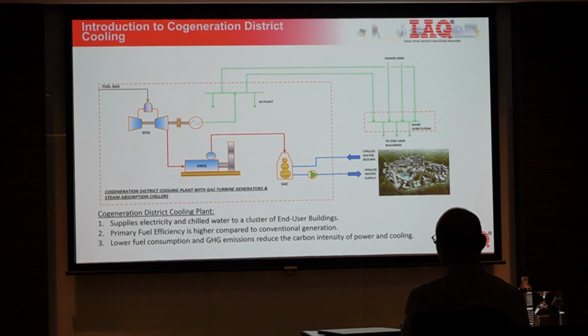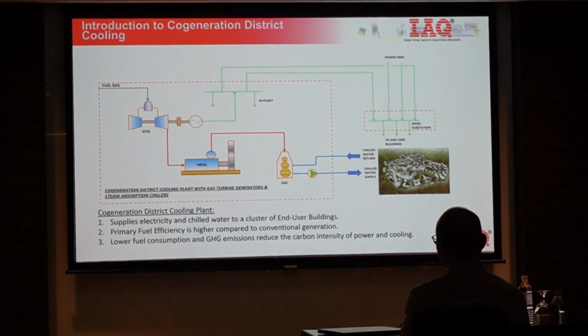So how it works? This is what we call the cogen district cooling system. The cogen side, definition of cogen, basically you are generating dual source of energy using one single fuel source. So from here, you can generate power, you can generate steam. The steam can be used for your process, or the steam can be used for the steam absorption chiller to generate chill water.